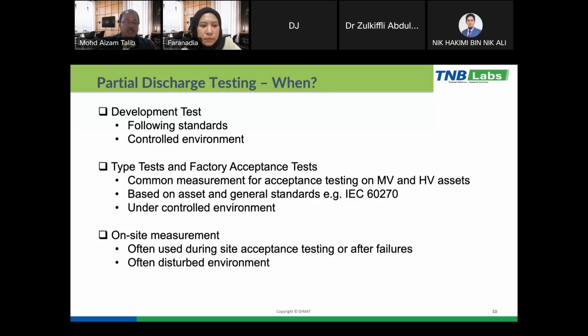And for the on-site measurements, as I said, after the delivery of the asset to the site, we want to ensure that the asset is good. We need to do the on-site measurements. And also sometimes when there is a failure of the equipment, we need to do the measurements. And then the measurement is normally done in a disturbed environment. So we need to have the filtering system, more advanced software, so that we can eliminate the noise.